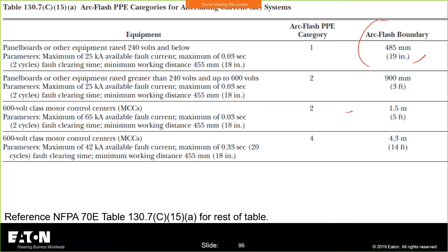And then it's going to give me my arc flash boundary, nice and simply. And what I have to do is I have to know what I'm working on. Let's say I'm working on a 240 volt panel board. And the next step in this process is I need to estimate the available fault current at this panel board.